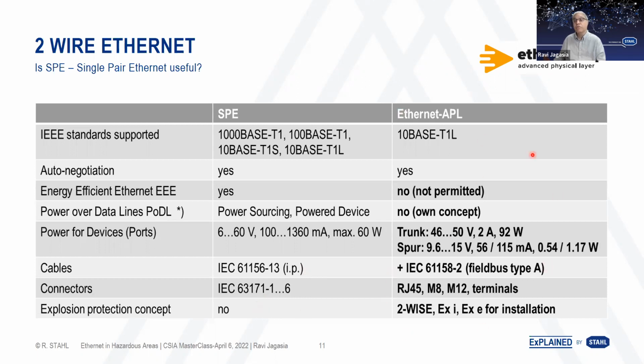What evolved was Ethernet-APL. They adopted the 10 base T1L. They definitely created their own power concept to ensure intrinsic safety. And then there was a trunk and spur configuration. Some of you may remember, Foundation Fieldbus had a similar trunk and spur configuration, and you could bring power into the hazardous area. They definitely used the standard available cable for the safe area, for the higher-level wiring of the Ethernet, but they also adapted the Type A cable from the FF world or even the Profibus PA world for this application.